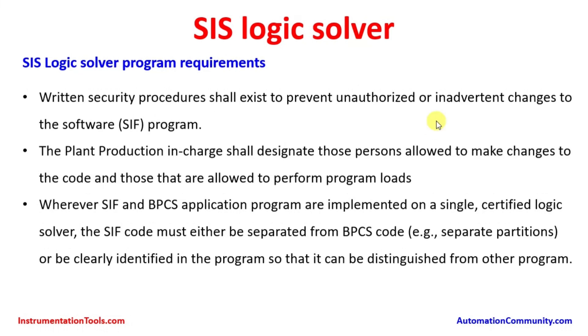Written security procedures shall exist to prevent unauthorized or inadvertent changes to the software program. The application program can be accessed, modified, and edited only with approval from the department leader or a concerned authority. They will maintain a list of persons authorized to work on those systems. The plant protection in-charge shall designate those persons allowed to make changes to the code and to perform programming loads — only authorized persons can make changes.